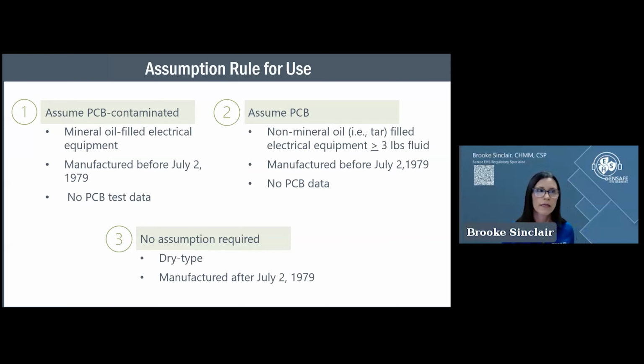The assumption rule says there's technically no requirement to test your equipment if it does not say 'no PCBs' on the nameplate from the manufacturer—you don't have to sample or know the content. But you have options if you choose not to sample, and different assumptions depending on the type of equipment. If you have mineral oil electrical equipment manufactured before July 2nd, 1979, and no PCB data, you assume it's PCB contaminated.